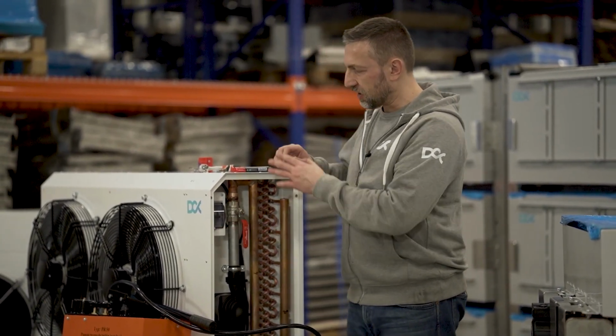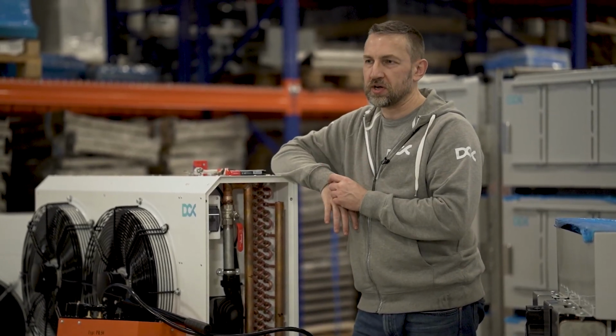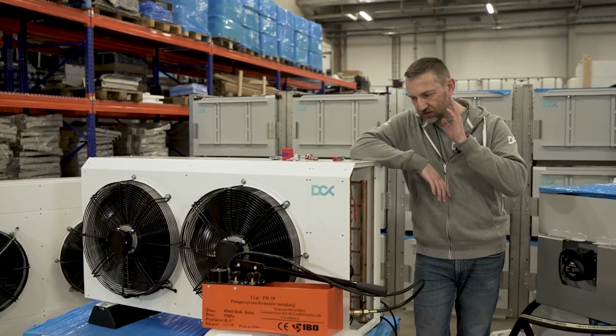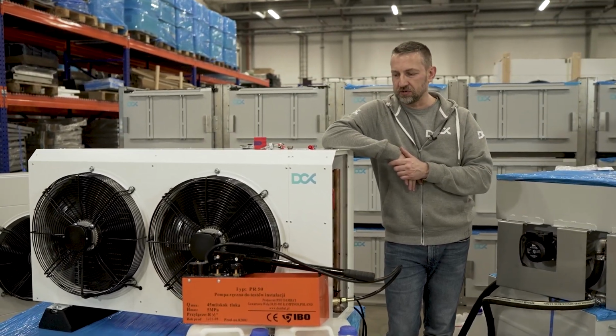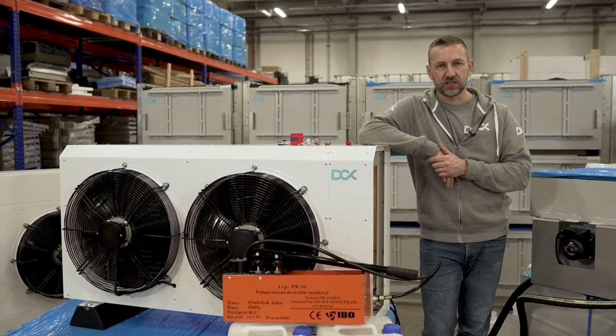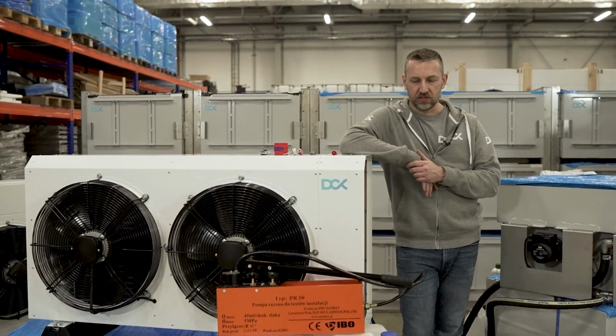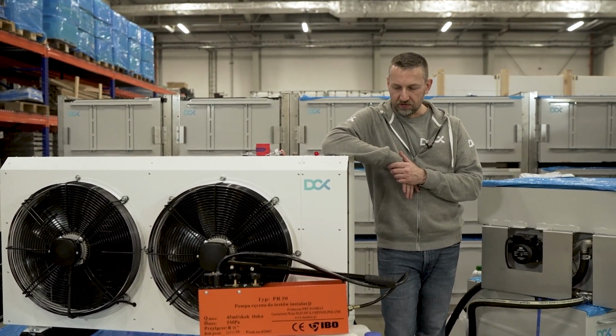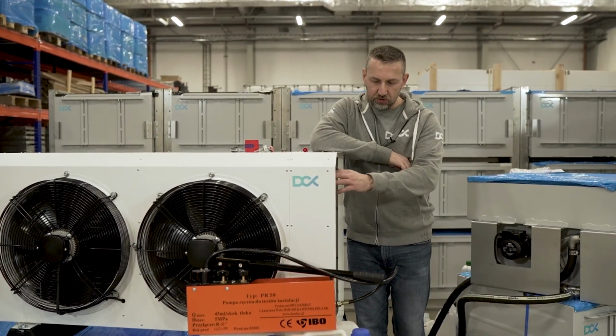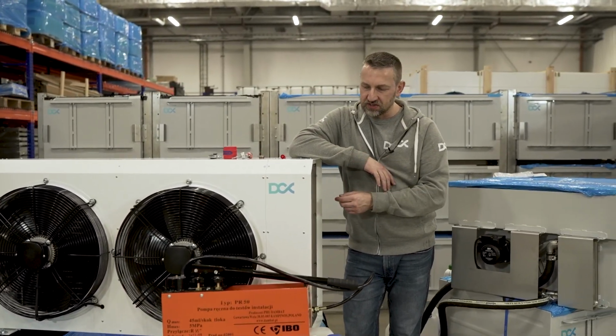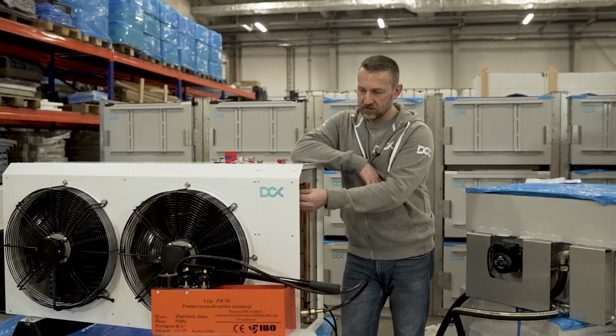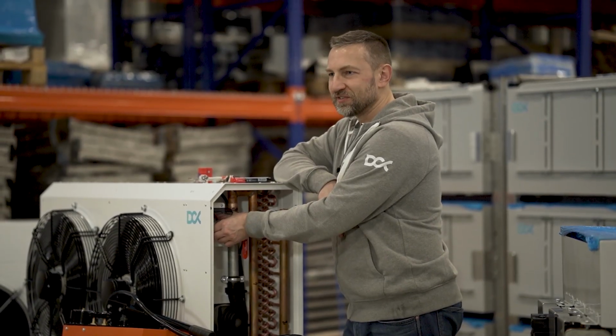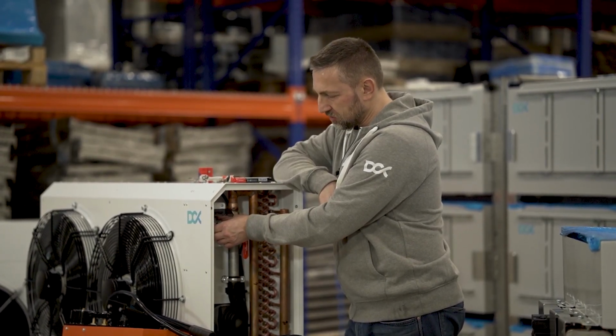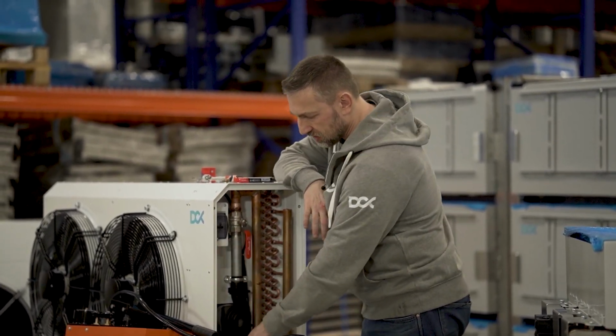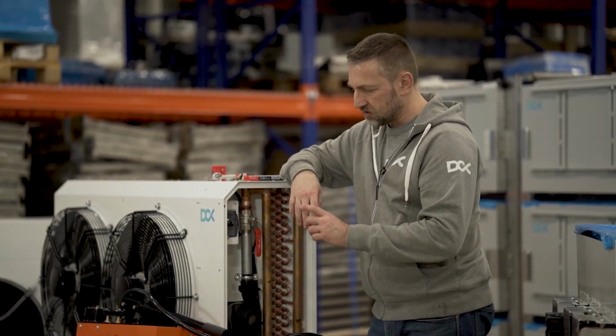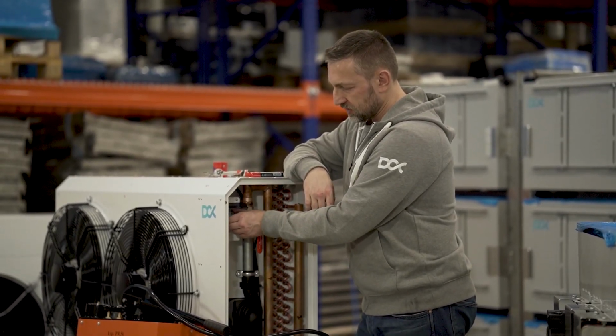You can run the ICP40 in 2 modes. One is the full mode, so fans are running at full speed. You can hear all the noise from those fans, and there are some videos which show the noise of the fans in real life. You can run that at 100%, or you can run that in the adaptive mode. So let's start the fans running in the adaptive mode. In the full speed, so 100%. I'm switching on the breaker W, and the switch on the ICP40 is on 0, so we are not starting that.